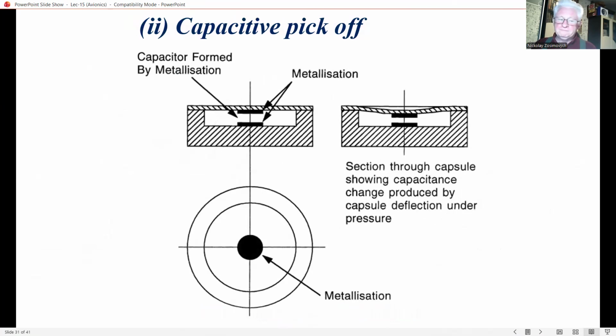Capacitive pick-off. An alternative technique is to deposit a metallic film on an area at the center of the diaphragm to form a capacitive element, or pick-off, whose capacitance changes as the diaphragm deflects under the pressure. This forms part of a capacitance bridge network, and this figure shows the device construction and how it works.